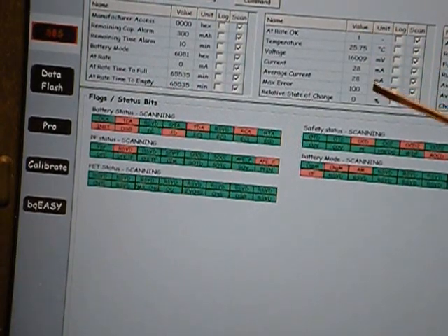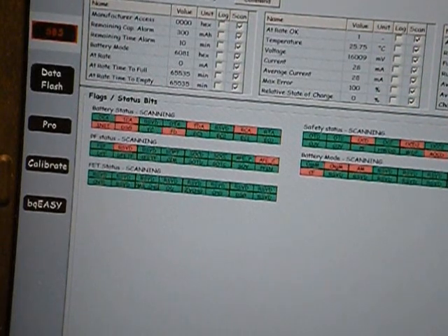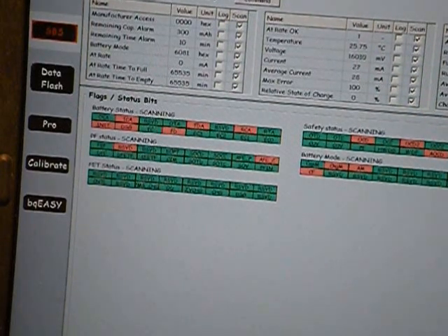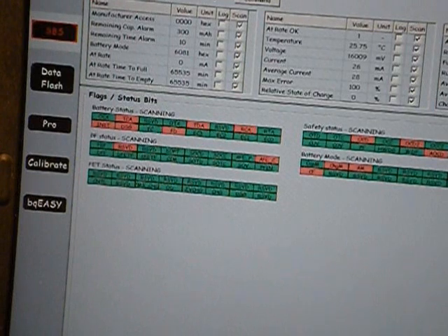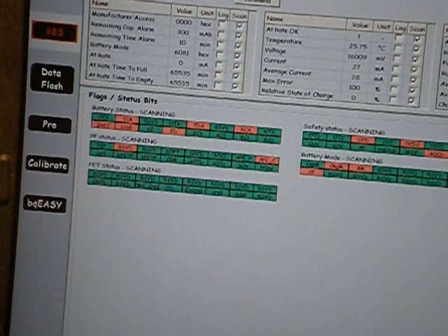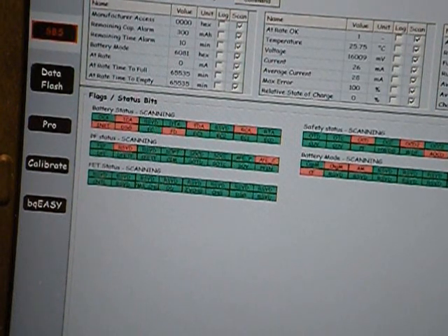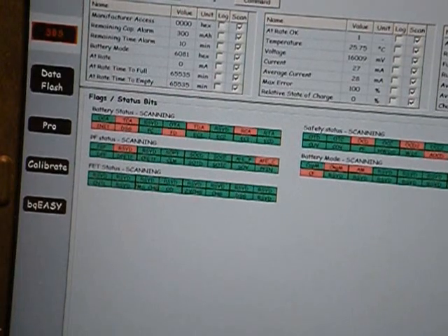You can see that the current we have is 28 milliamps because we have the current sensor simulator set to nominally 0 volts, which would correspond to about 0 amps out of the BMS.